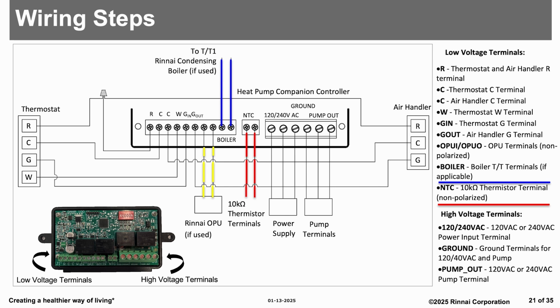Now we'll move on to the high voltage section. Again, we'll work our way from the outside in. The three terminals on the far right are the pump terminals. The outer two are for hot and neutral. Note, these are interchangeable. And the third one is the ground terminal. After connecting those, your final connection will be to the power supply, which are the three remaining terminals.